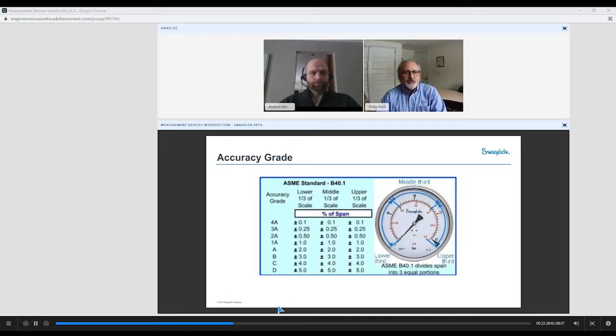And next slide. So gauges have an accuracy range. They're laid out in what are known as the lower third, the middle third, and the upper third. Pressure gauges are typically most accurate in the middle third of the gauge. So this would be where they're most accurate. The gauges we provide have the same class all the way across the gauge, all three equal areas.